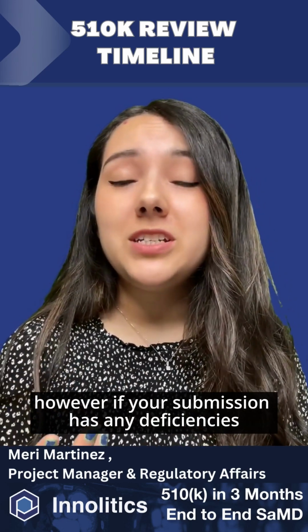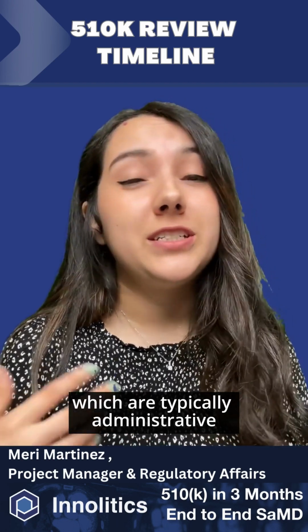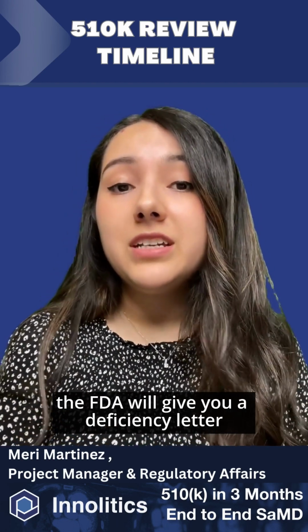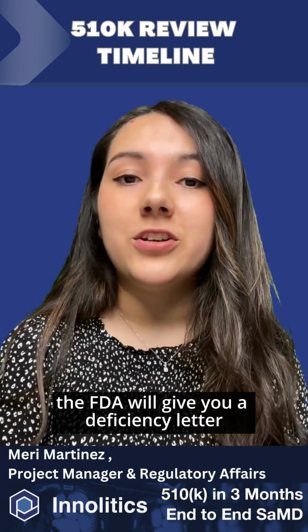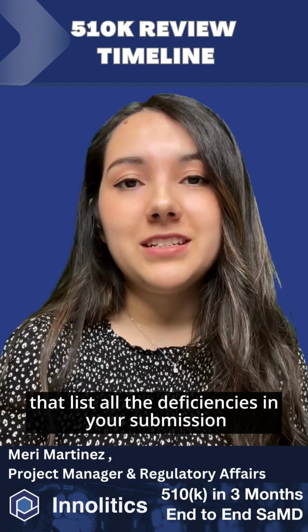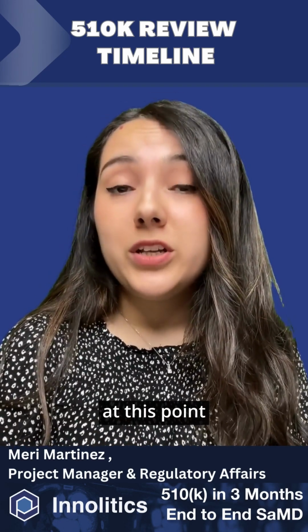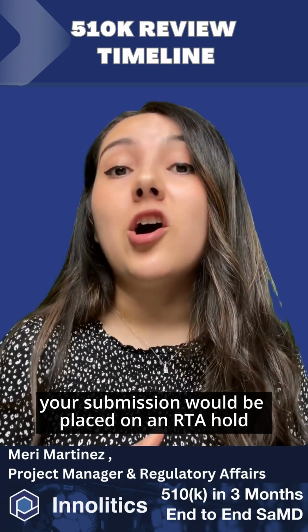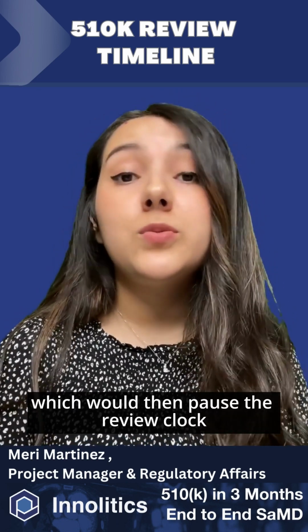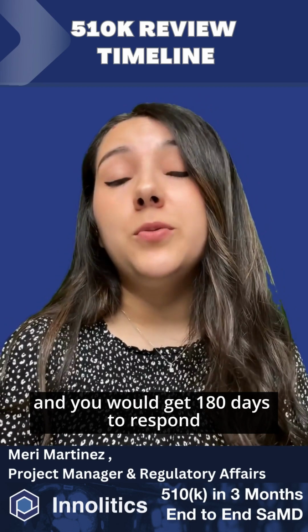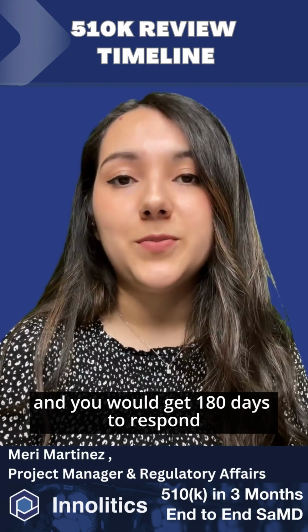However, if your submission has any deficiencies, which are typically administrative, the FDA will give you a deficiency letter that lists all the deficiencies in your submission. At this point, your submission would be placed on an RTA hold, which would then pause the review clock and you would get 180 days to respond.